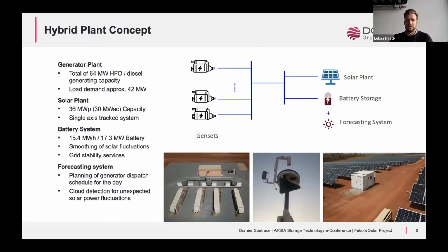Focusing on the next 12 hours, operators in the morning have some idea of the generator dispatch schedule. What I'd like to point out on this slide is, as you can see from the simplified diagram, the battery and the solar plant really form a combined system. So engines never see only the solar plant, it's always filtered through the battery. The battery has a chance to absorb or discharge power in addition to the solar power, which allows us to have a stable grid at the gensets, at the mine level.